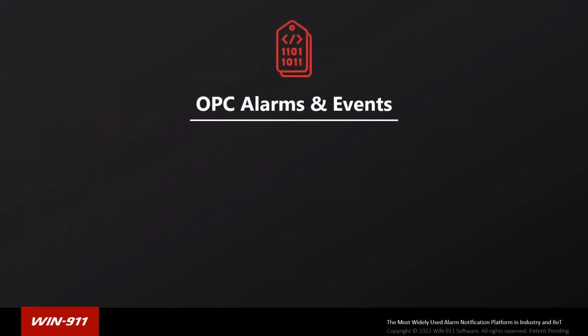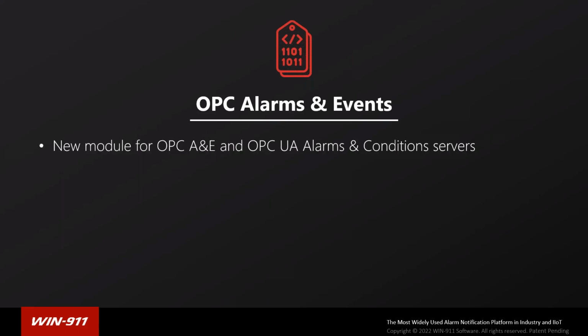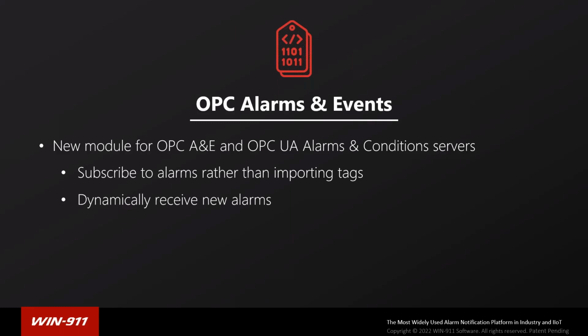All right, so that's it for the data access module. The other new module that we released was the alarm and events module. What this does is we've added support for OPC Alarm and Events Classic and OPC UA Alarms and Conditions. Those are two different server types. Rather than import tags like everything we've been talking about, you just subscribe to an alarm server and you start receiving alarms. It's very similar to our Factory Talk alarm and event server connection if you've used that before. And it's basically a direct connect using OPC A&E or A&C.